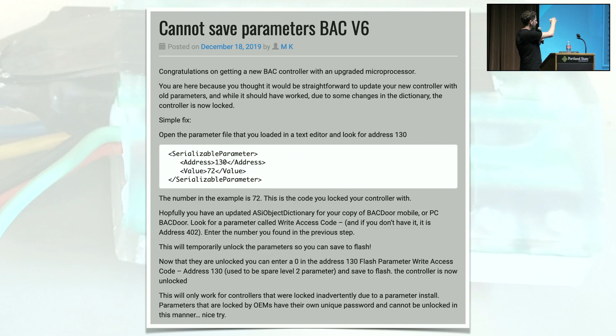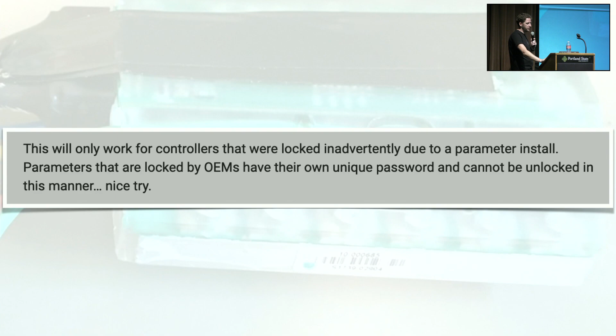Now that's cool and exciting. Basically what they say is you could look in that XML document for register 130, because they took a register that was used for something else and made it a locking register, and people were accidentally overwriting that locking register with some random value. So you look for the value you had in yours and put it back in. But it will only work for controllers that were locked inadvertently due to parameter install. Parameters that are locked by OEMs have their own unique password set by the OEM and cannot be unlocked this way. Nice try. And really, that's your tone? It's the wrong tone.